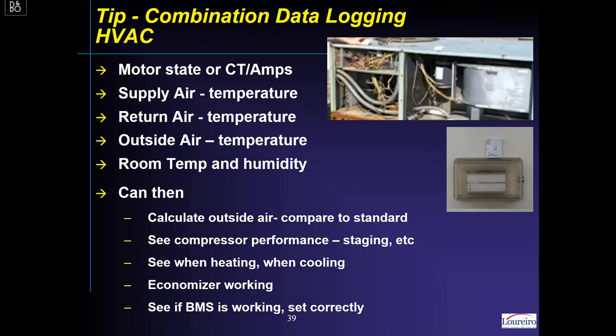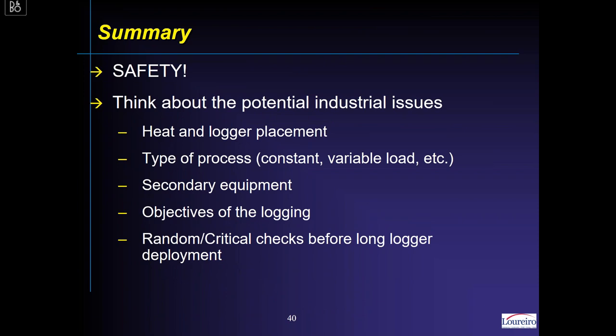Another combination logging example: HVAC equipment — a rooftop unit. We'll put motor state loggers or CTs on both the motor and the compressor, and also use temperature loggers for supply air, return air, and outside air so we can calculate the amount of outside air being used and mixed air temperature. Once you do all that — with a logger on the thermostat as well — you can see how all the systems are working together, or not.